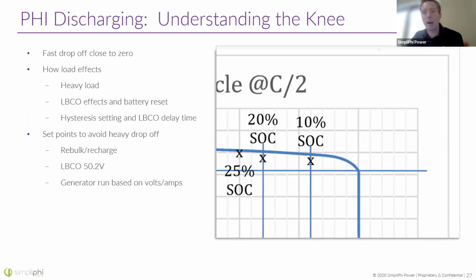If we cycle a battery from 100% state of charge to 0% and back, we're only going to expect about 3,000 cycles out of it. If we change that so we're only dropping the battery from 100% to 20% state of charge, yes, you're losing a little bit of battery capacity, but we expect 10,000 cycles out of that battery. If we limit it to 10% state of charge, I think the number is 6,000 cycles. So 10,000 cycles, if that's daily, adds up to 26 plus years, and at 100% depth of discharge with 3,000 cycles, we're looking at more like 10 years. So you can get a lot more lifetime out of the battery if you limit where you cycle it to.